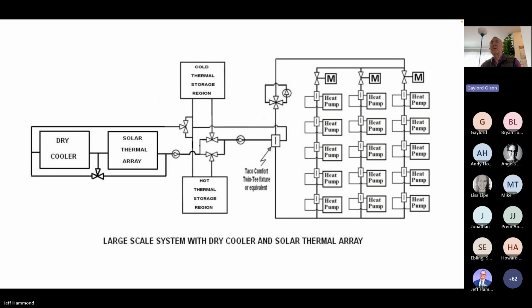However, if you have a system which has temperature measurement at all of those heat pump locations, temperature in the vertical flow direction, then you will know how much thermal energy each heat pump is either using or putting into the system. And you know the temperature in and out of the Taco Comfort Twin T fixture that's shown there.